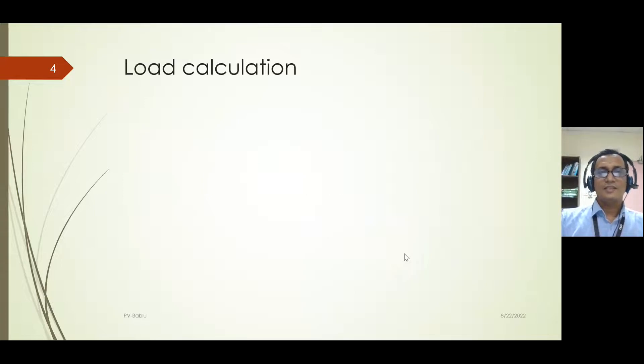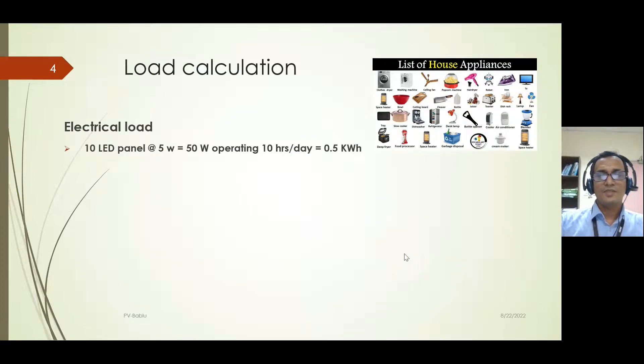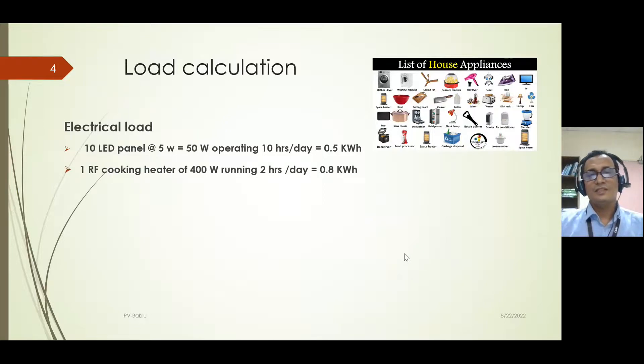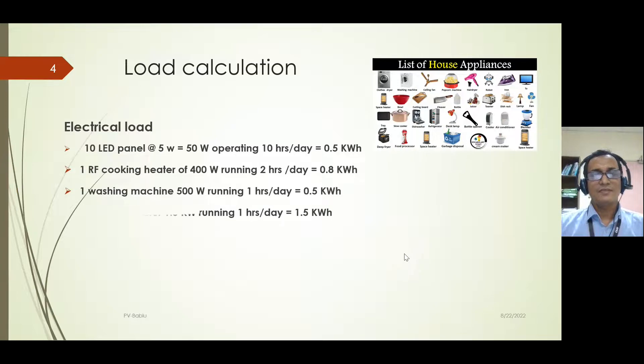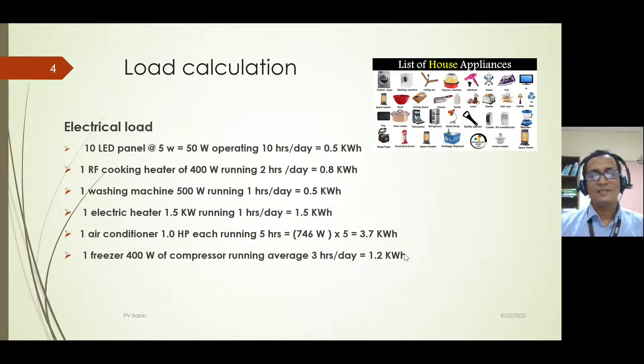The first step is load calculation — how the household will be supported by the panel installation to provide power for the grid-connected PV system. For this household the appliances are: 10 LED panels consuming 0.5 kWh, an RF heater for cooking at 0.8 kWh, a washing machine at 0.5 kWh, an electric heater at 1.5 kWh per day, an air conditioner at 3.7 kWh per day, and a freezer of 400 W capacity running efficiently at 1.2 kWh per day. Total electrical consumption is around 8.2 kWh per day.